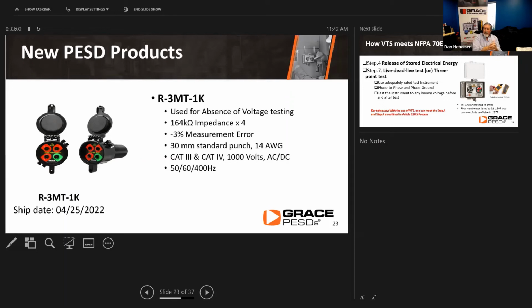It's used in varying worlds, but as we go to more and more high voltage DC applications and high voltage AC applications, we're getting more and more requests for this type of product in the automotive world and the solar world and others. And really what we've done is we've added 164 k ohm impedance. In this case, it affects the typical multimeter, which is basically a 10 mega ohm, the most common. It gives you a variance of about 3%.